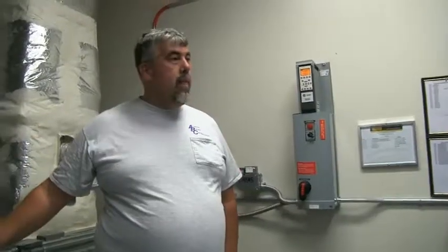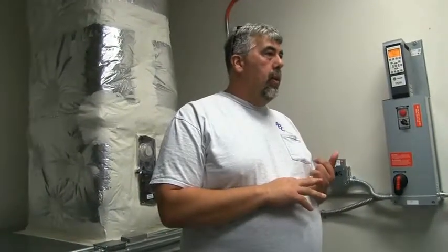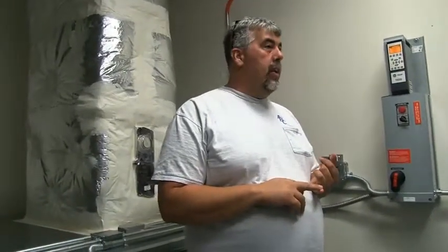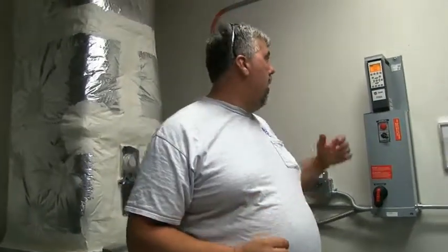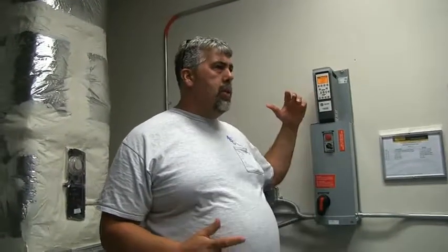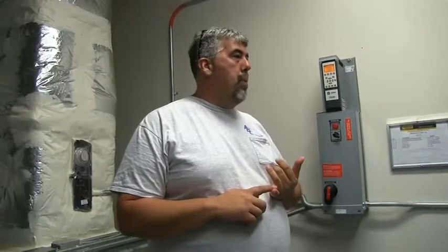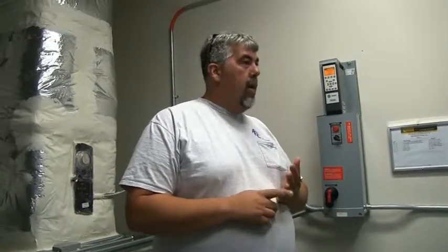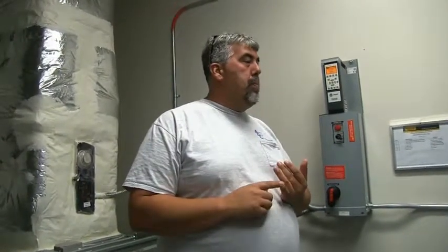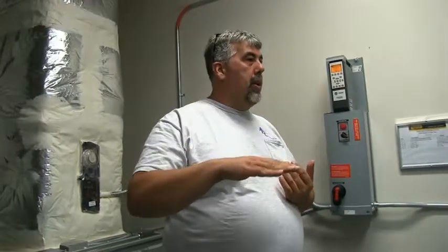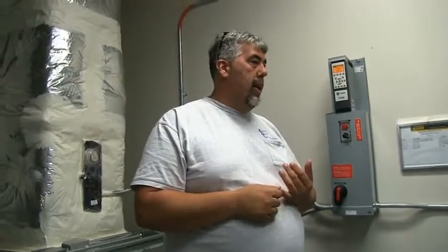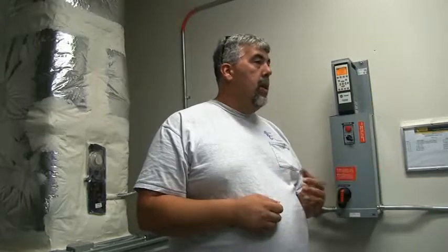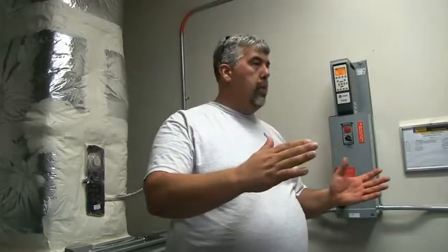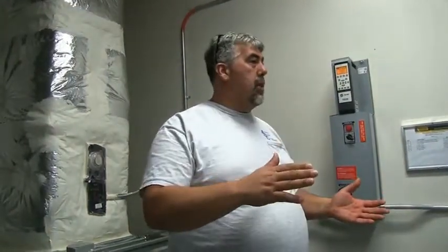This is one of the VFD air handlers, and it's controlled based off of static pressure. It does have a static pressure reset, so don't be alarmed if you come in and this is ramped way down and you're going, why is it ramped down? It's because, per sequence, if all the boxes are below 65% open, it will actually decrement the static pressure down by 1/10 of an inch at a time, every 15 minutes, until the boxes float between 65 and 76%.